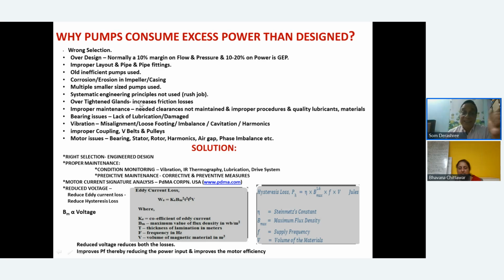Over tightened glands sometimes will also increase friction. Improper maintenance: needed clearance between the impeller and the casing increases, then the backflow will increase and you may not get enough head, etc. Bearing issues, lack of lubrication, damage, vibration, misalignment, loose footing, imbalances, cavitation, harmonics, all this will lead to improper coupling, V belts, etc. will also have a loss, and motor issues like bearing, etc.